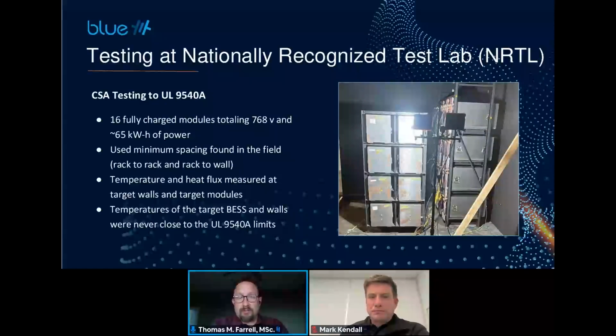And then ultimately they went to a lab, they went to CSA. And in order to do the test, they provided 16 fully charged modules, which ended up being around 65 kilowatt hours of power. They set up their racking to use their absolute minimum spacing that they would typically see in their applications. And that included both from rack to rack and rack to the nearest surface.